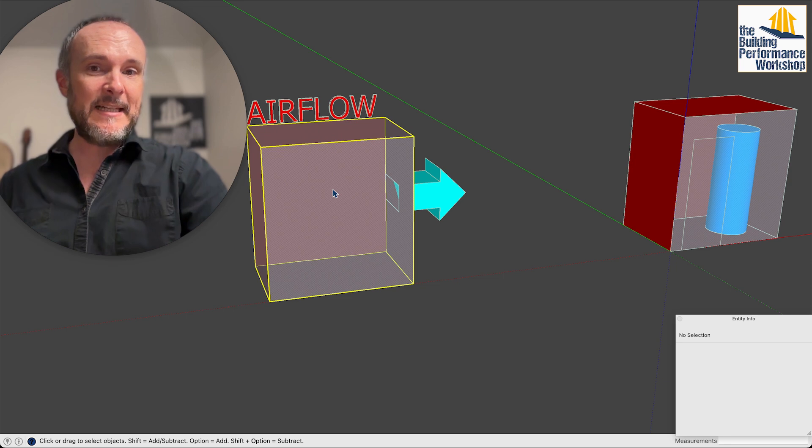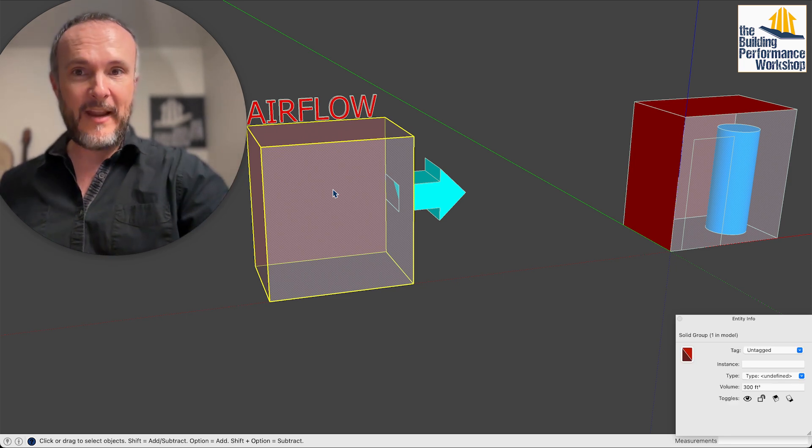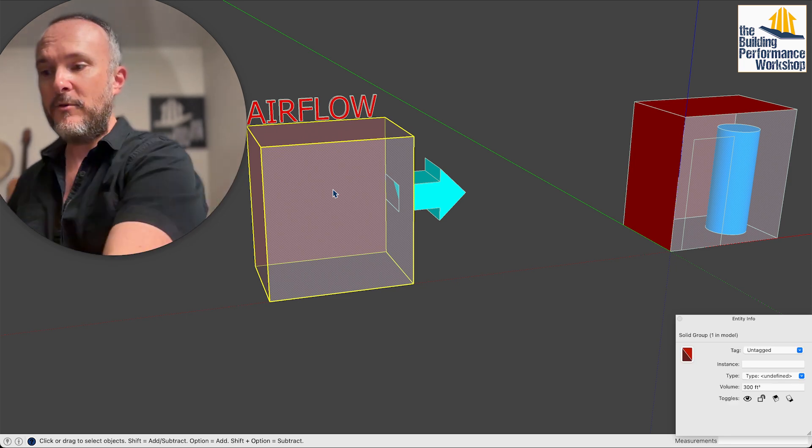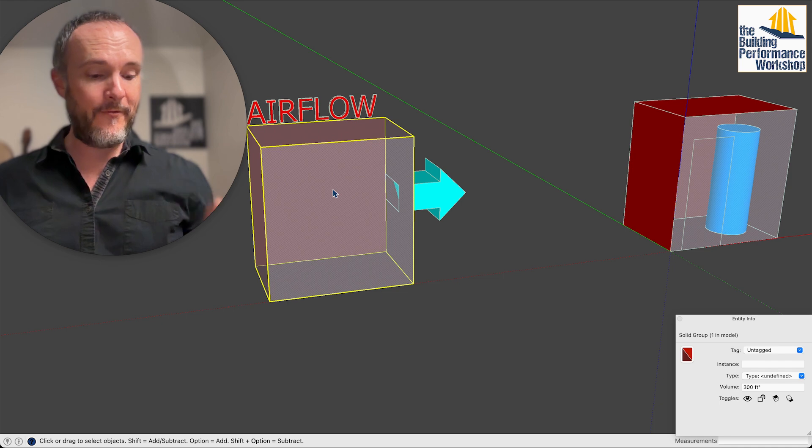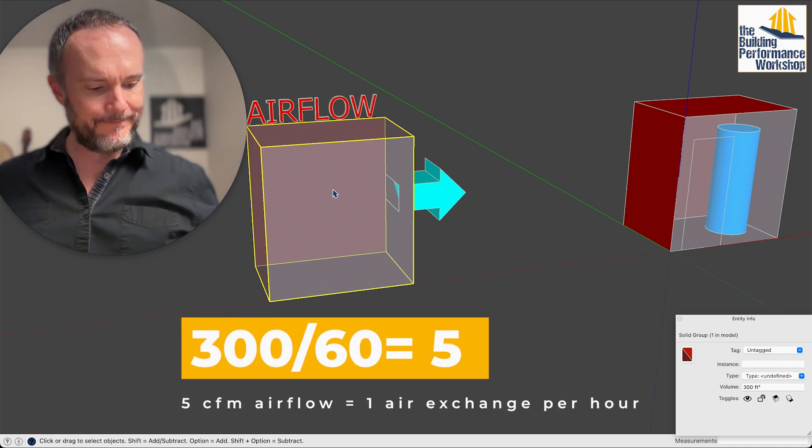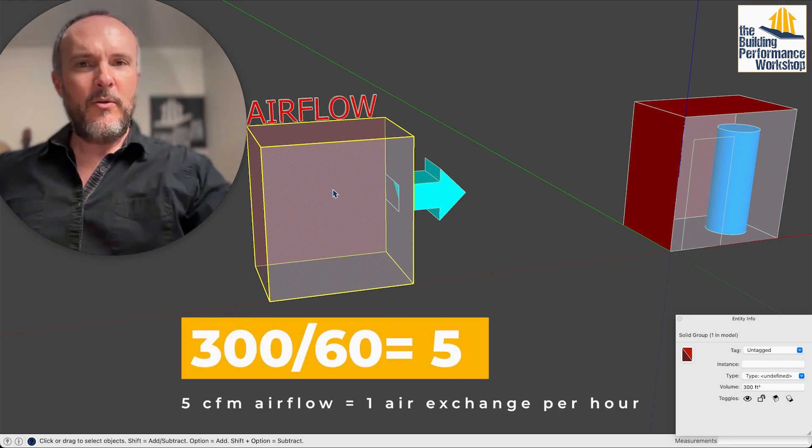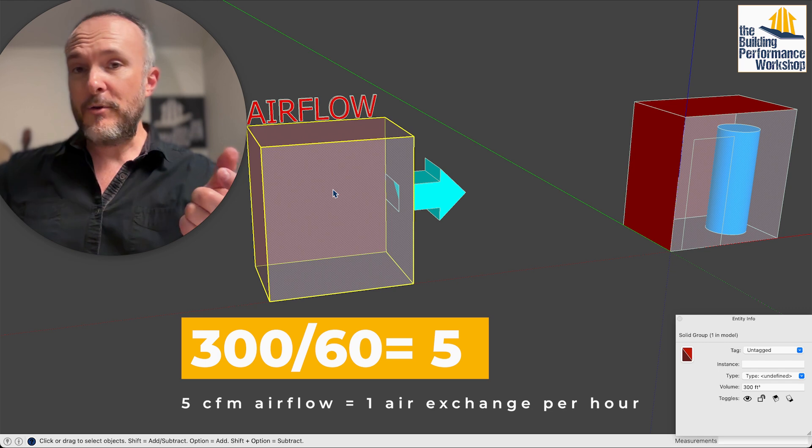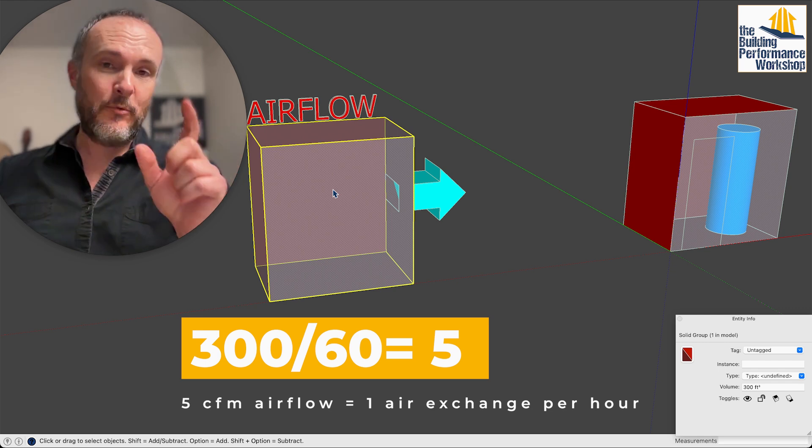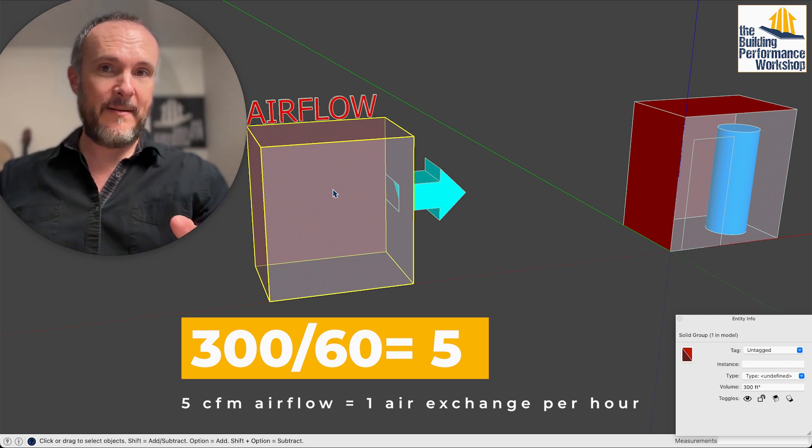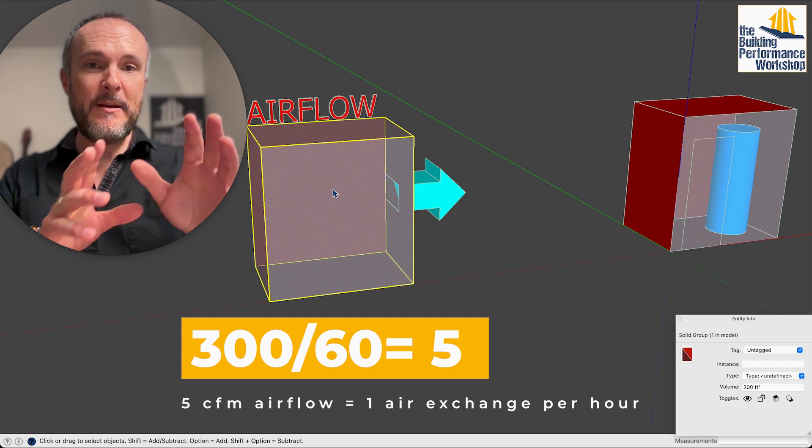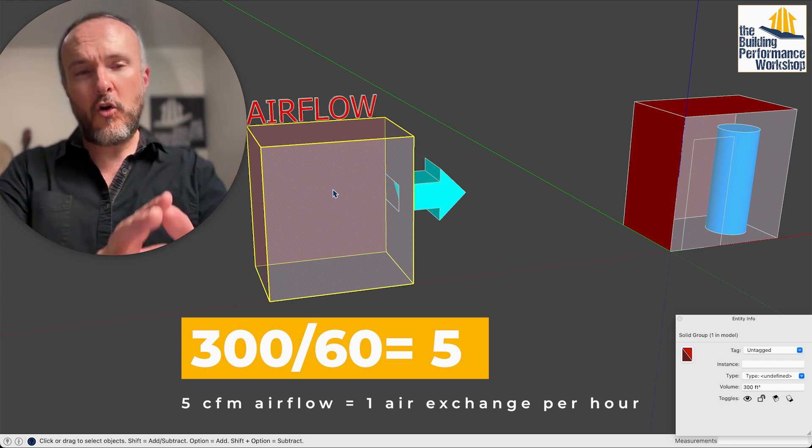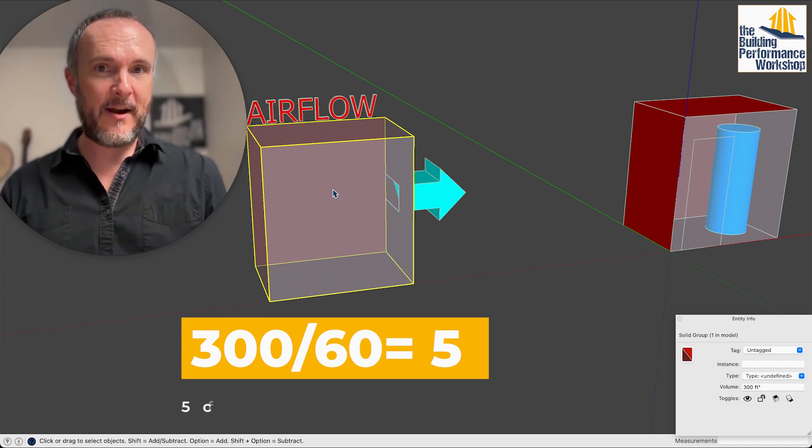Now this is 300 cubic feet of air again in that room and what you do is take any volume and divide by 60. So 5 CFM is a computer fan basically. If we ran a computer fan at 5 CFM 24/7, you would be replacing all the air in that room once an hour.